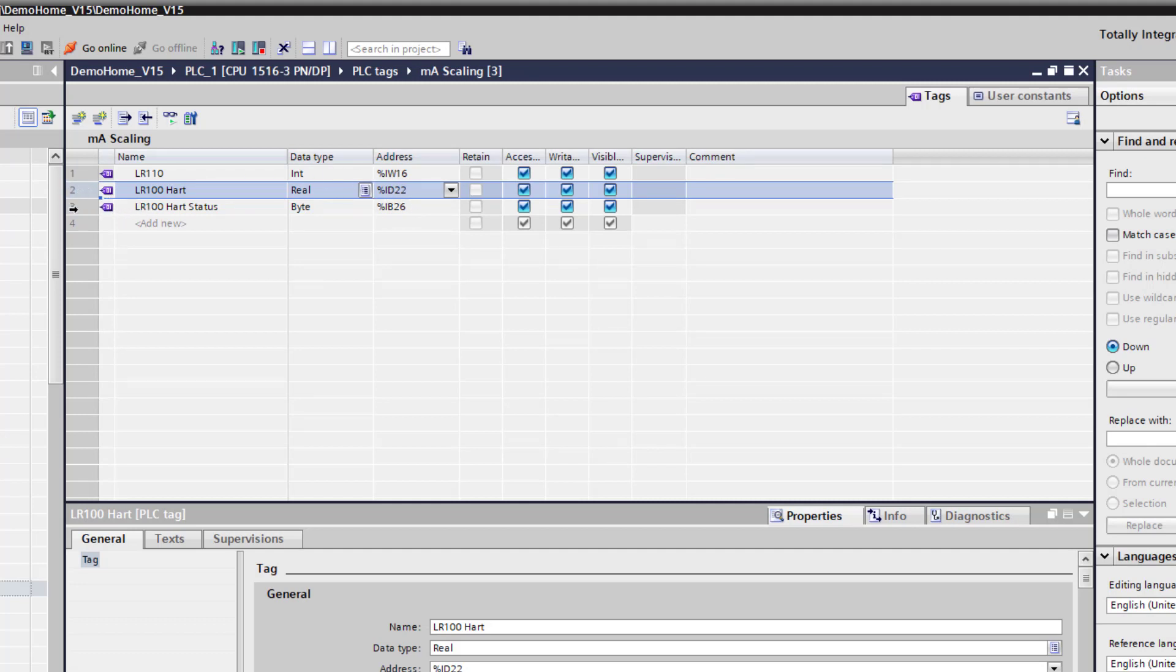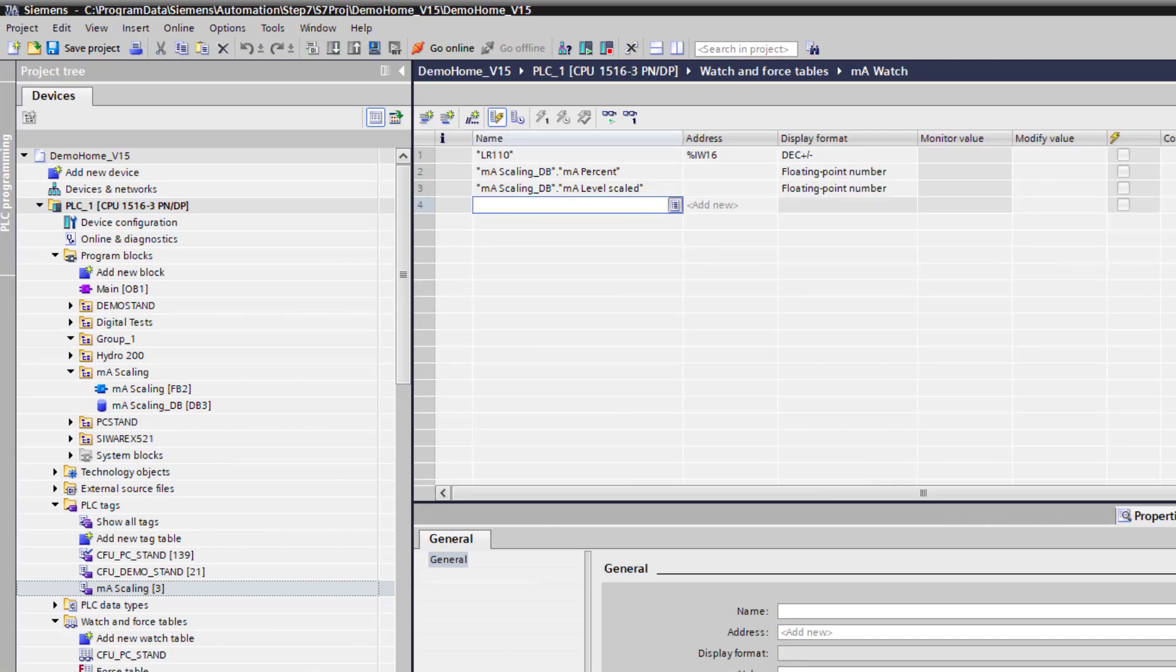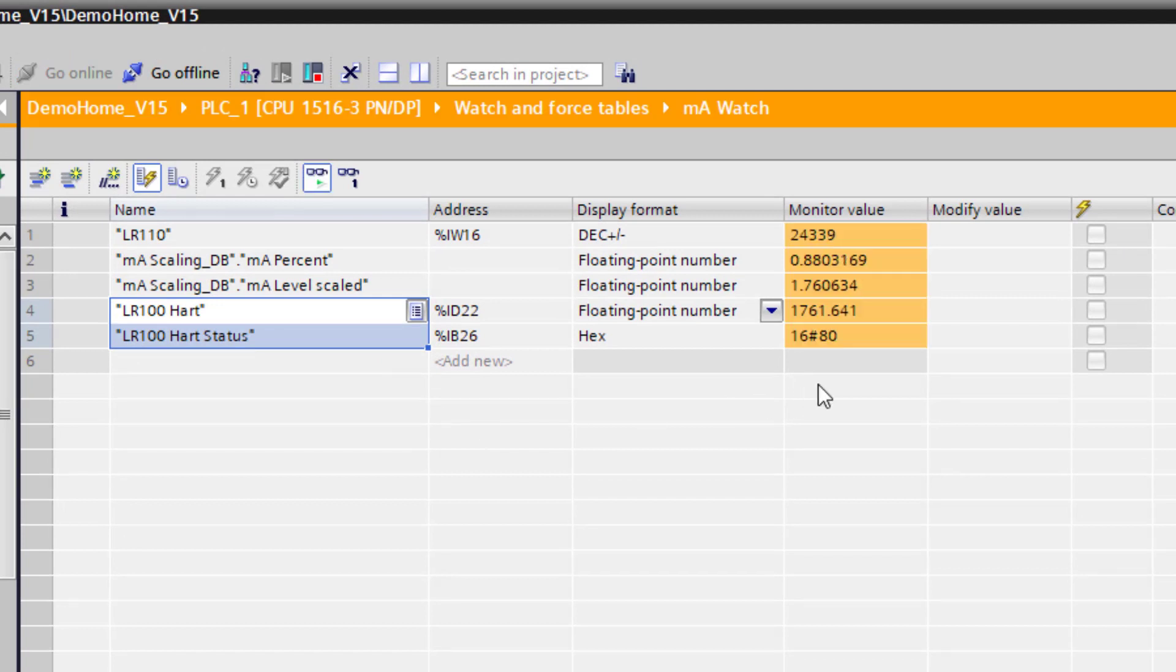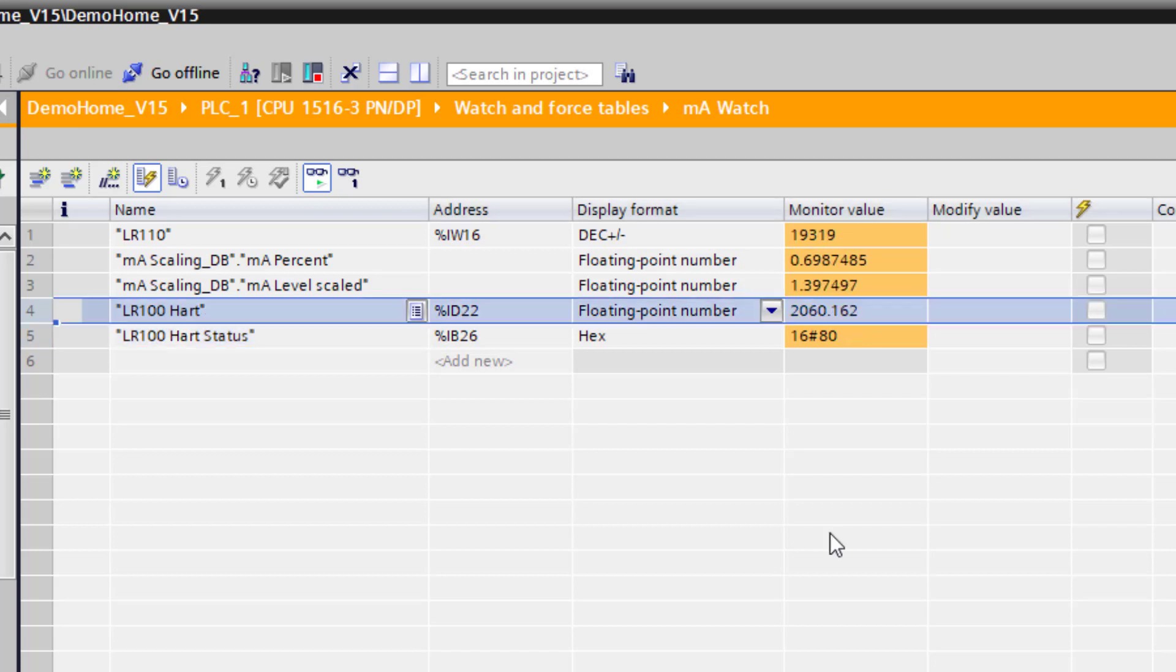So you can see all of the values working at the same time. So my unit is programmed in millimeters, not that it makes any difference. So you'll see the values changing. And of course, this is where I said that HART is a little bit slower. But if it's a simple level application, you can see here I'm moving the transducer up and down, and it's moving relatively fast. So if you've got an application where the level is moving, you know, say 10 centimeters in a minute, this will more than easily cope with that. So there you have it: scaling of your milliamp input and your HART value coming from a Sitrans LR110 radar.